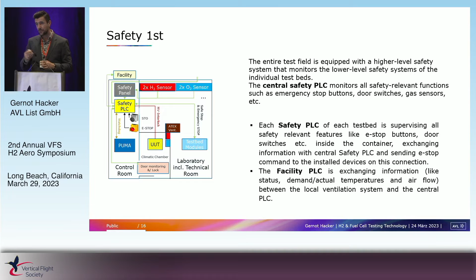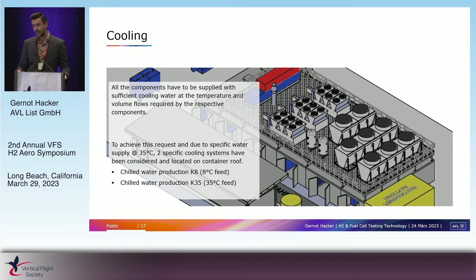Cooling. As I mentioned in the 101, we learned that cooling for fuel cells is a topic. With 1.5 megawatt fuel cells, it's even more of a topic. There is no standard solution off the shelf available. There was also a specific request that the supply water needs to have 35 degrees C, so we had to install two specific cooling systems. Because of the small footprint, we could leverage the second story on top of the containers here, so we have chilled water production for 8 degrees C feed and 35 degrees C feed.